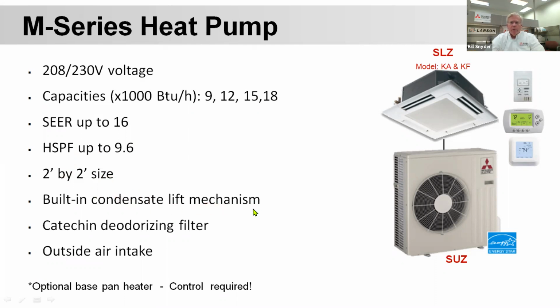It's not a pump. Because the drain is actually below the ceiling, it literally sucks water out and slings it out the side. So it literally lifts it up and out towards the top of this unit, and it doesn't pump, it just lifts the water out, and then you gravity feed from here into a drain or into another pump if you have to pump it someplace.